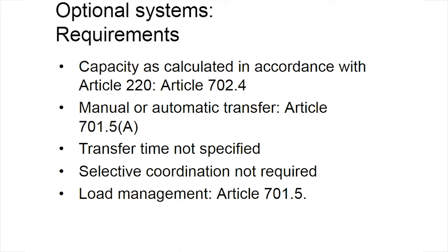Transfer can be either manual or automatic. There's no particular transfer time specified, and selective coordination is not mentioned in Article 702. It's generally good practice to design for selectivity, but they're certainly not the highly restrictive all upstream devices, all possible fault currents, all possible trip time rules that govern Articles 701 and 700. Here's another item: the mention of load management should be Article 702.5 rather than 701.